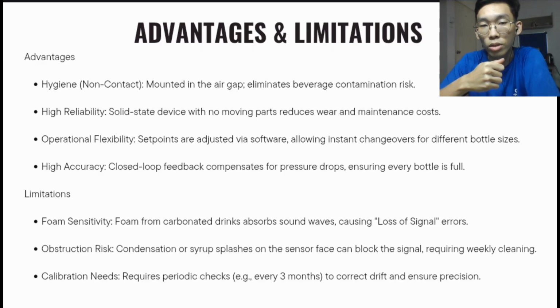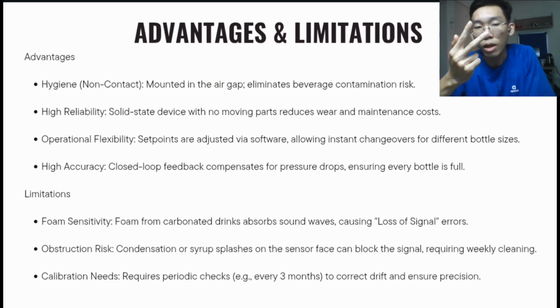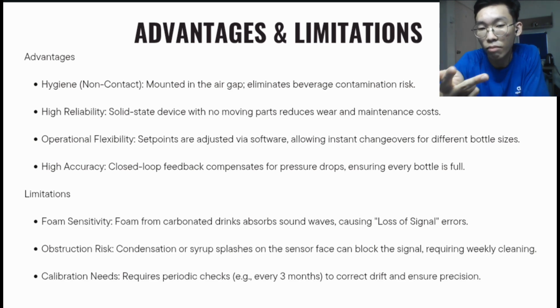The ultrasonic sensor offers 4 distinct advantages, which we mentioned just now. The first one is hygiene, because it is mounted in the air gap. It is non-contact. This eliminates the contamination risk common with mechanical flow switches. The second one is reliability. It is a solid state device with no moving parts, meaning it won't wear out or jam like the mechanical switch. Third, flexibility. The fill levels are digital, so we can switch the bottle size instantly in the software without stopping the line to move the sensor. The last one is accuracy. The most important, it provides the closed-loop control. It reads the actual level, ensuring the valve only closes when the bottle is truly full, solving the underfilling issues.